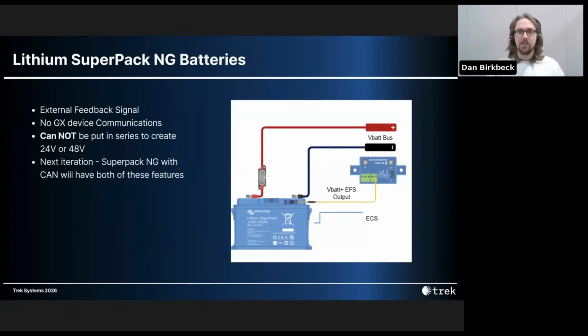The EFS activates when the configured low SOC warning threshold is reached in Victron Connect and stays active until SOC rises above that threshold. The wiring diagram here illustrates an example using the EFS to control a Battery Protect with its remote on-off port. Some limitations of the SuperPack NG batteries to note.